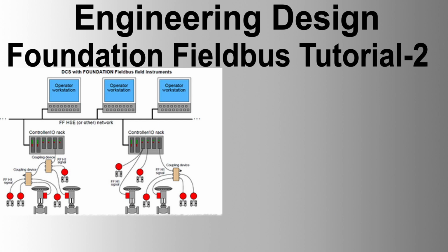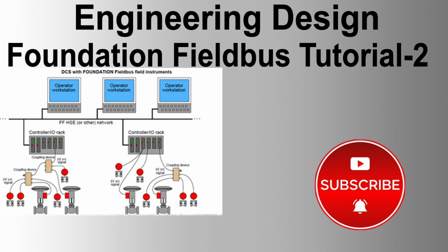Example applications. Simple measurement, AI1: the transducer block gives measured value in the desired unit. Scaling in AI, AI2: the transducer block gives measured value in a unit and the AI block converts it into another unit. Orifice plate flow meter, AI3: the transducer block gives measured differential pressure with an orifice plate, and the AI block converts it into flow rate by calculating the square root of differential pressure.